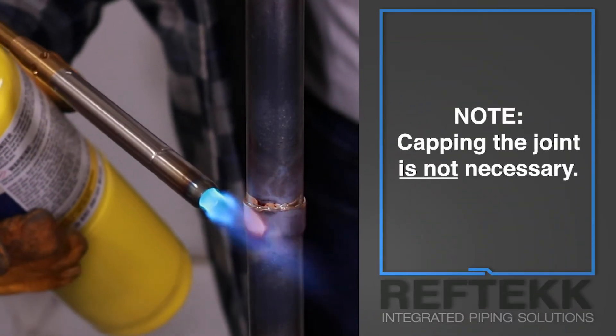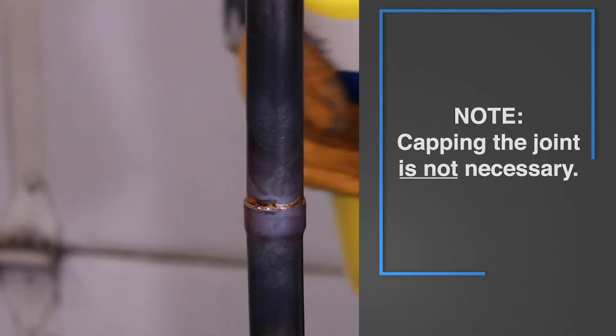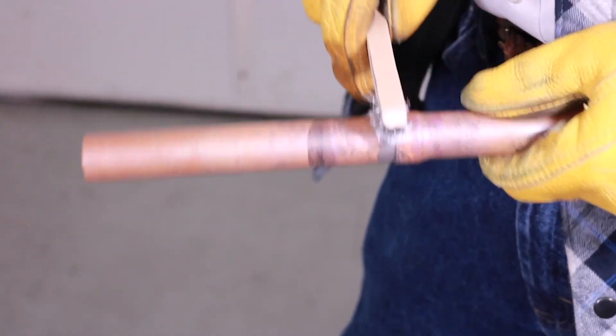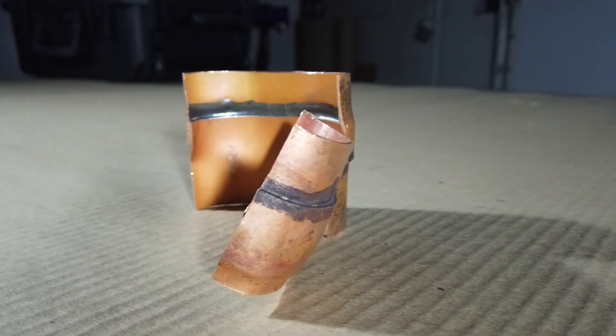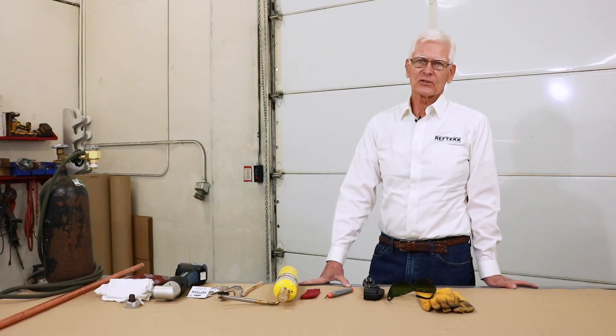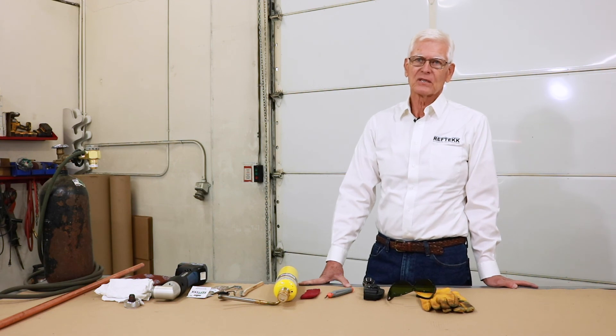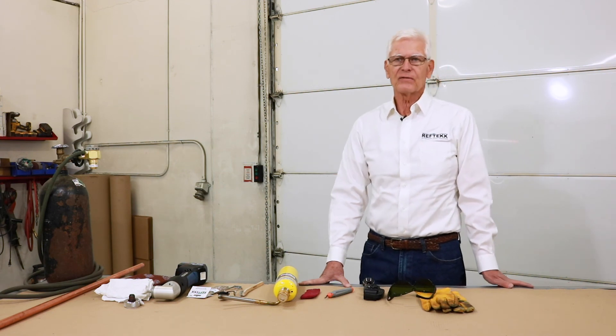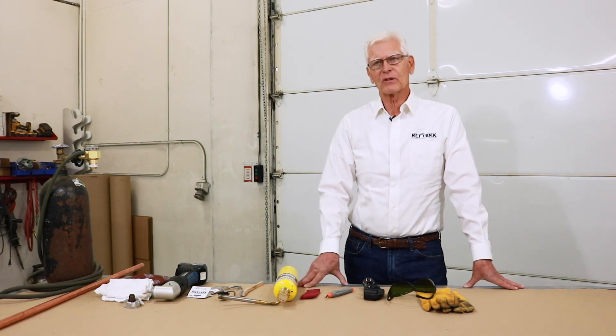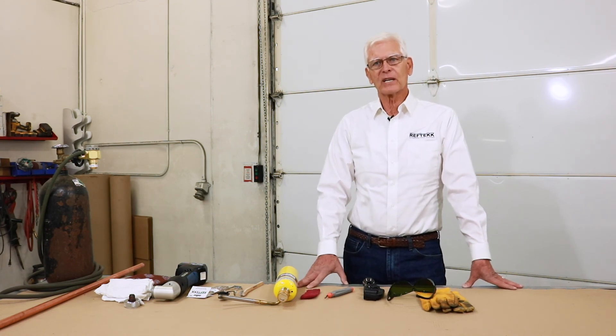We've created a properly brazed joint. It only required one braze as opposed to two traditionally required when using store-bought couplings, reducing the leak potential by half. Brazing is kind of like painting your house — it's all in the prep. The actual brazing is the easy part. Good tools, good materials, and proper preparation make the difference. REFTEKK H55 tubing, brazing rings, and the SwageX tool give you the best chance for a first-class brazed copper piping system. Thanks for watching, and don't forget to watch our other videos.